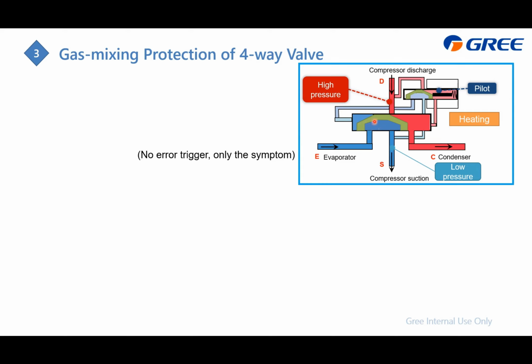Here is the slider, this one, and there are 4 ports. D connects to the compressor discharge, the S port is connected to the compressor suction side, E is for the evaporator, and C is for the condenser. And here there is a pilot valve. Actually, this is the small size 4-way valve. You can also find this one, it is the capillary. It is connected to here to detect the high pressure, and this one into here to get the low pressure.